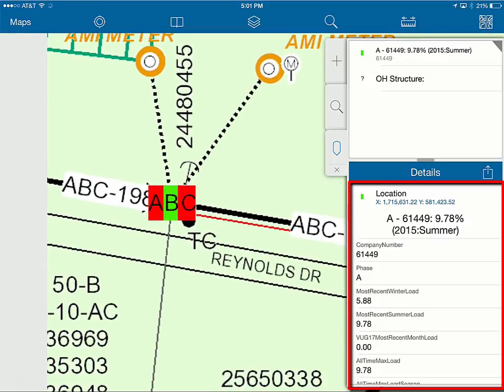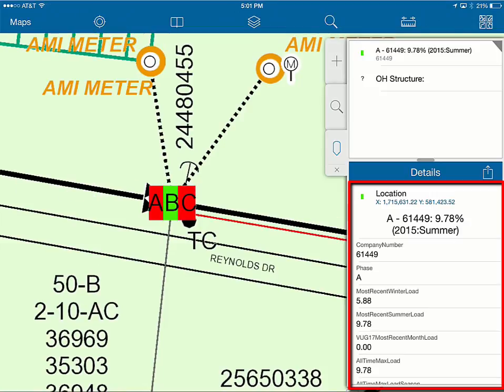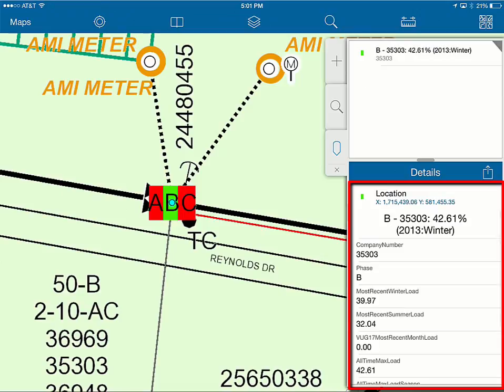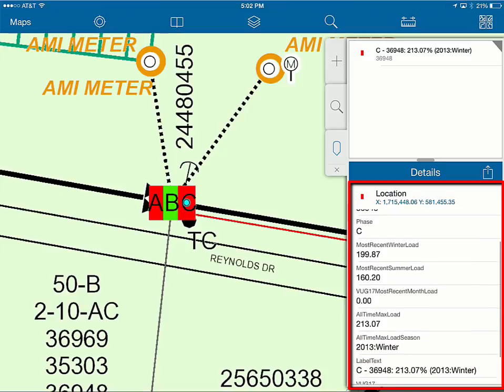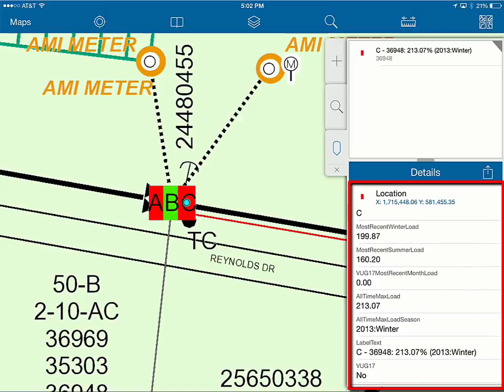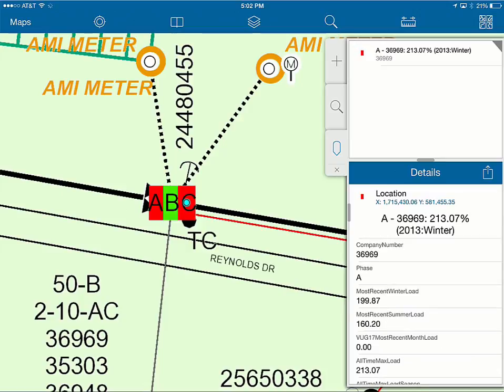Let's zoom over to this other transformer — an interesting one because it's a three-phase overhead, and as you can see, all three phases are represented individually with different colors. In this case, if we were replacing the B-phase, that transformer would not be an issue as it's only loaded at 42.61%. However, A or C might be a different case. Looking at the details for the C-phase, it's loaded at 213% — the most recent winter load was 199%, the most recent summer was 160%, and the all-time max was 213% from the winter before last. This transformer is pretty heavily loaded, and if it blew out we'd want to replace it. Transformer A is also loaded at 213%.